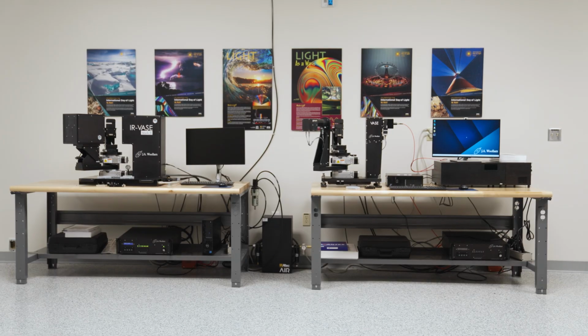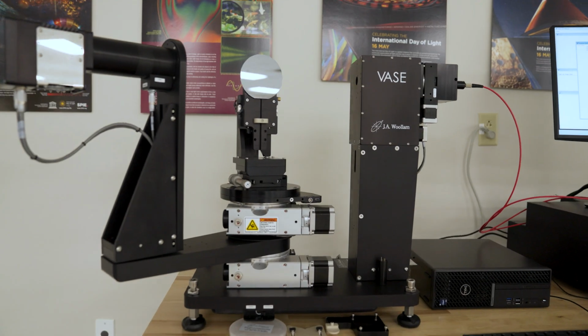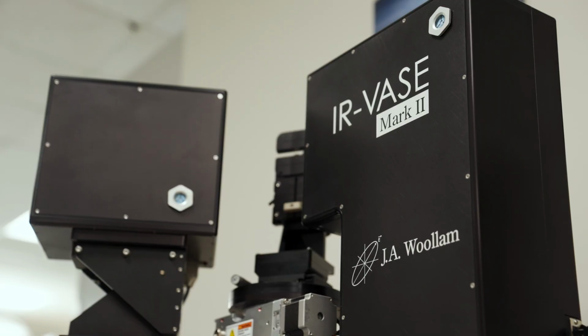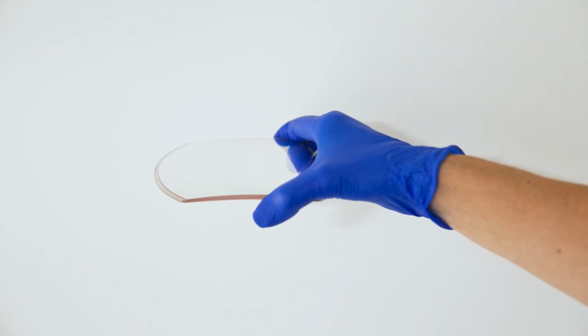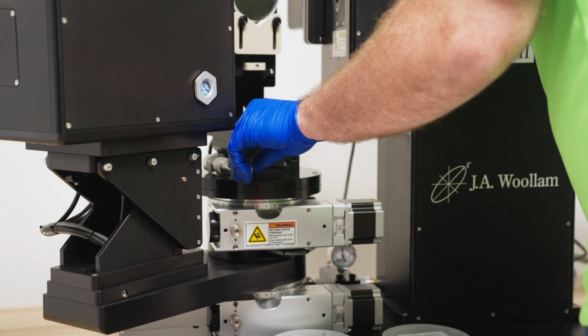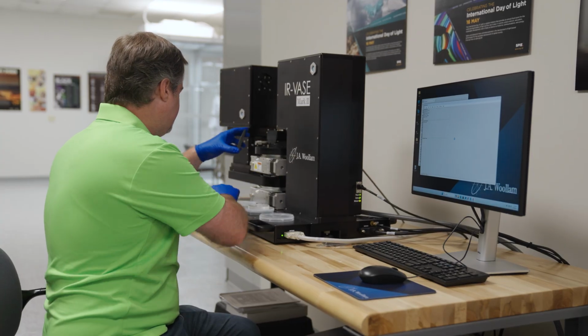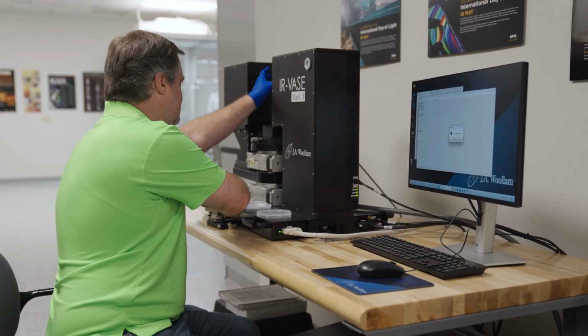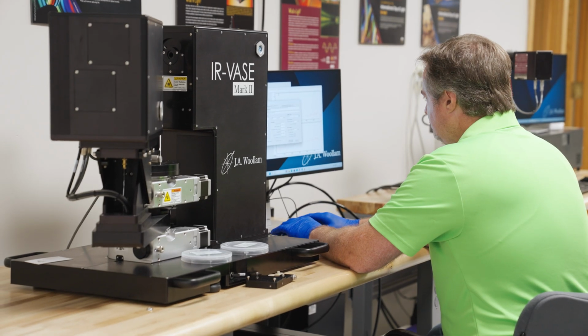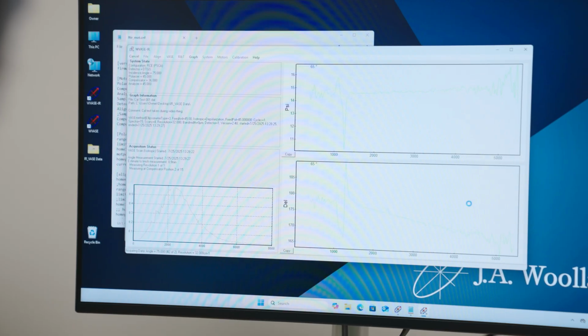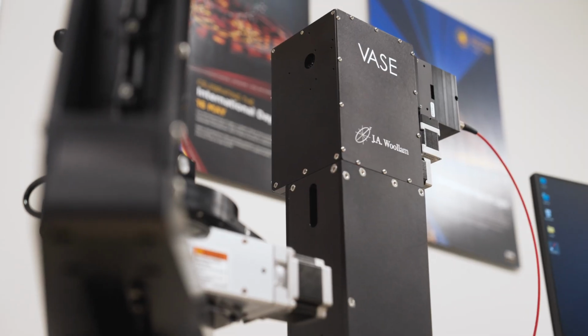Here we have two ellipsometer measurement systems. So these are both from Woollam Instruments. We have a V-VASE ellipsometer and then an IR-VASE ellipsometer. Both these take spectral measurements, but using input and output polarization measurements, you can determine a lot of features of thin film samples. So if you have a sample with substrate, thin film, or many layers of thin films, you can figure out things like the index of those thin films, how light reacts to the films, their spectral characteristics. We can go all the way from UV wavelengths all the way out to 40 micron wavelengths.